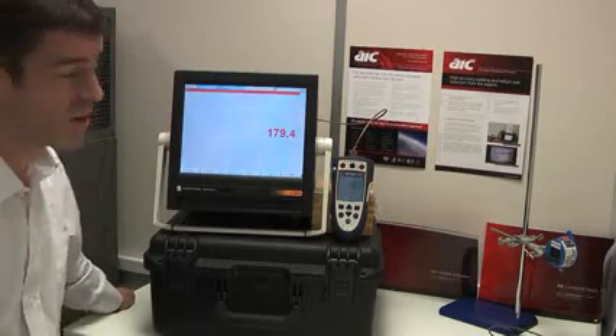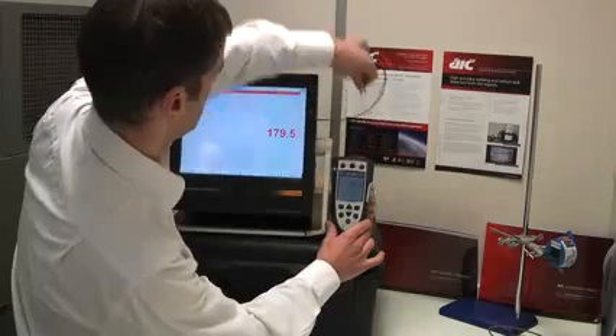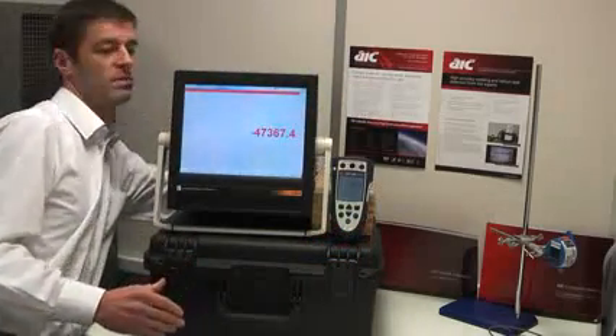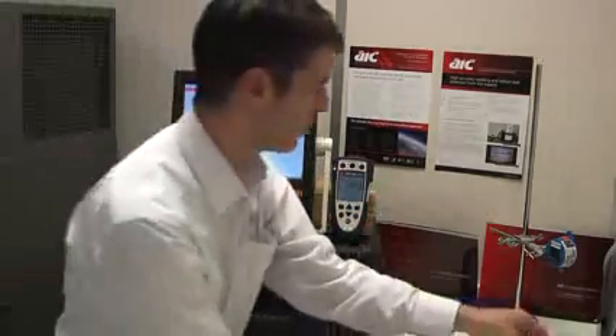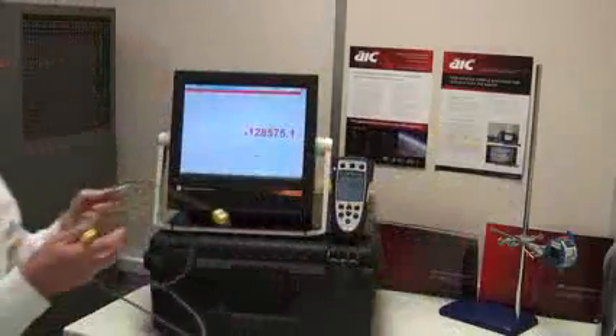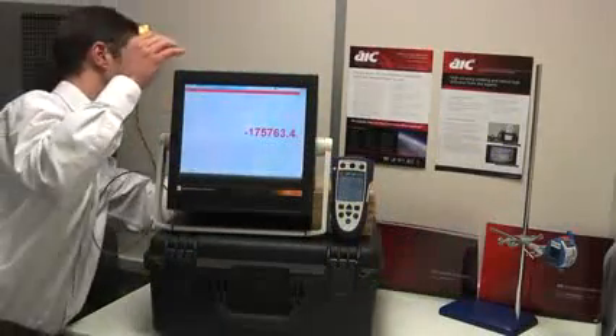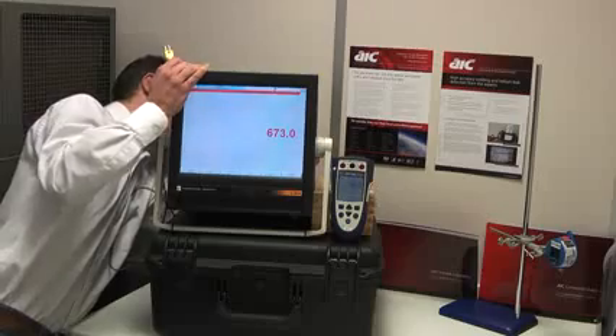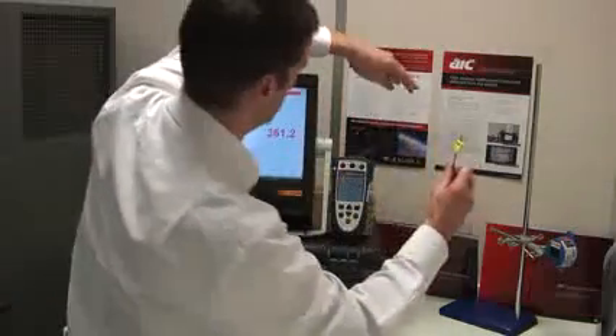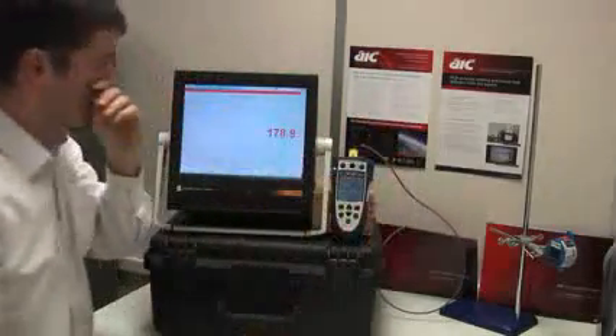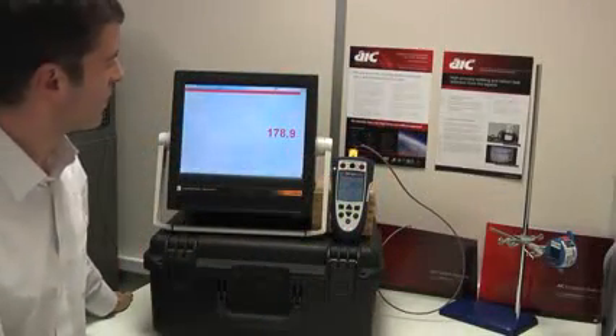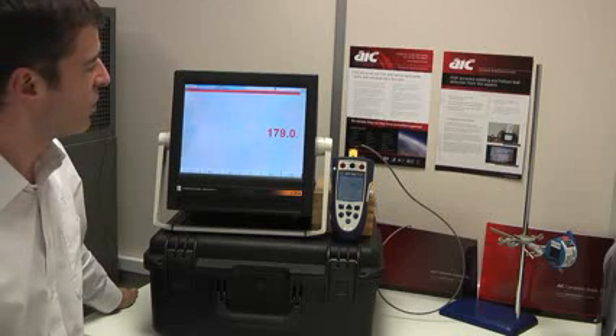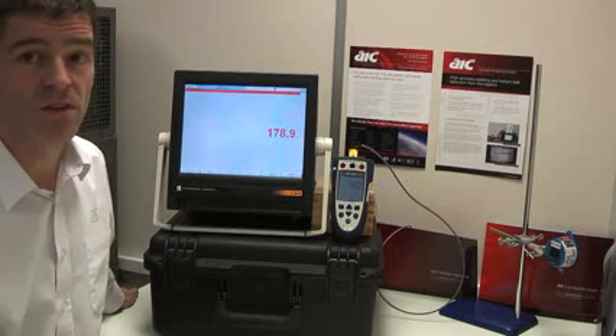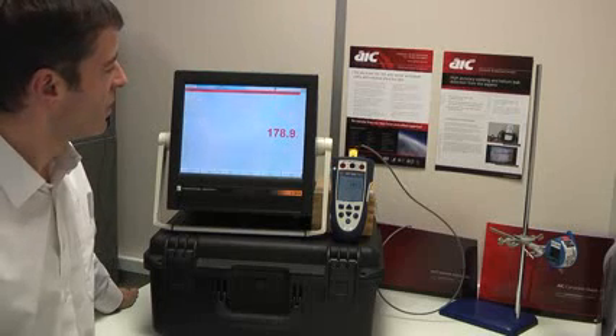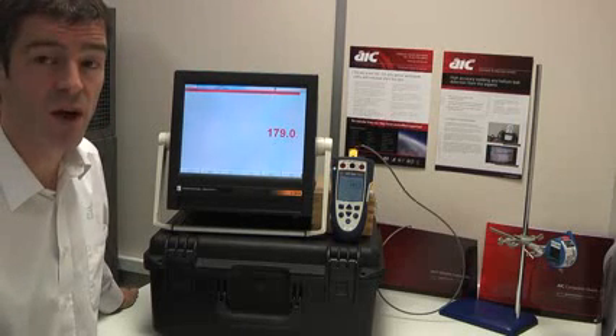And just to really drive the point home, instead of using thermocouple cable at all, just use a piece of copper wire. Plug that in there. It's obviously a copper wire. Shouldn't make any difference at all, but because the temperature gradient is 0 along the cable, the copper wire introduces almost no error into the system.